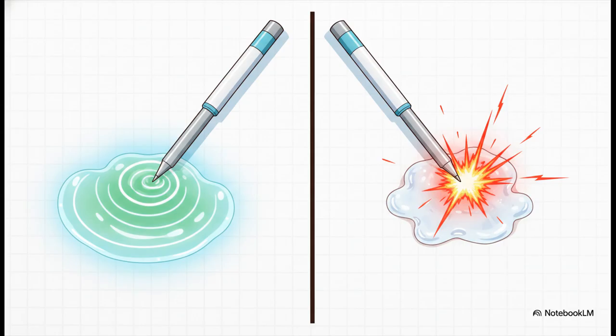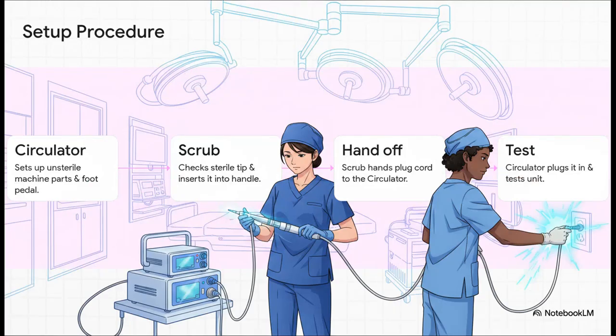These are tools that use electrical current to cut tissue or stop bleeding. Before use, the inactive electrode has to be covered with a proper electrocardiograph contact paste to safely pass the electricity. The strict warning here is to never, ever use a standard lubricant like KY jelly. Because it's non-electrolytic, it actually insulates the electrical contact. This forces the current to concentrate and push through thin portions of the jelly, which will cause severe, localized burns to the patient.